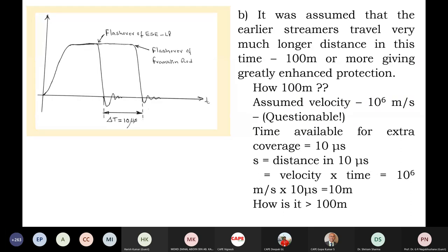And they have assumed that the earlier streamers travel a very much longer distance in this time, 100 meters or more, giving greatly enhanced protection. How did they arrive at this 100 meters? They assume a velocity of 10 to the 6 meters per second, which is highly questionable. The time available for extra coverage, according to them, is 10 microseconds, which is the time differential between the flashover timings of the flashover wave shape for the ESE and for the Franklin rod. Now, what is the distance in 10 microseconds? If you take the simple product of velocity multiplied by time, it comes to only 10 meters. 10 to the 6 meters per second multiplied by 10 microseconds is only 10 meters. How do they claim 100 meters?